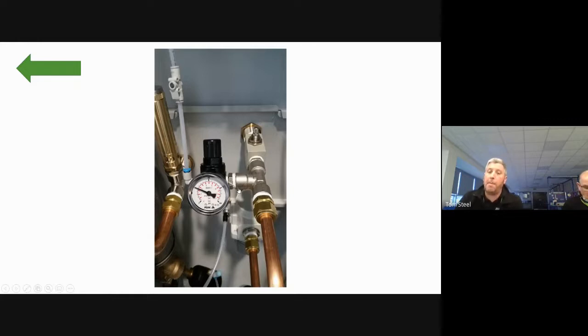Don't overflow the capacity of the generator. And it's not just for our generator, it's for any system that supplies a known quantity, a known purity of gas. If you increase the output flow or the pressure without compensating for that with larger compressors, filtration, and everything that goes with that, then you will affect the purity. And that's the most important thing to remember.